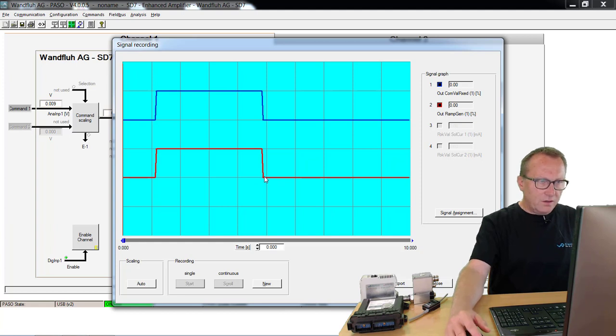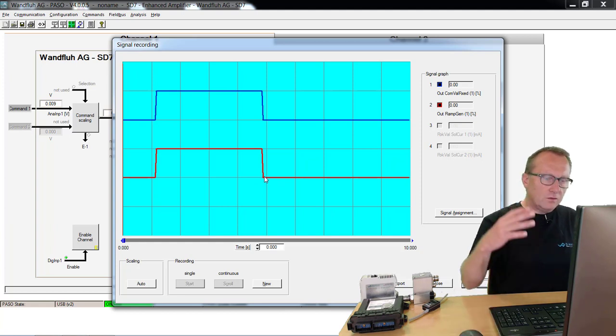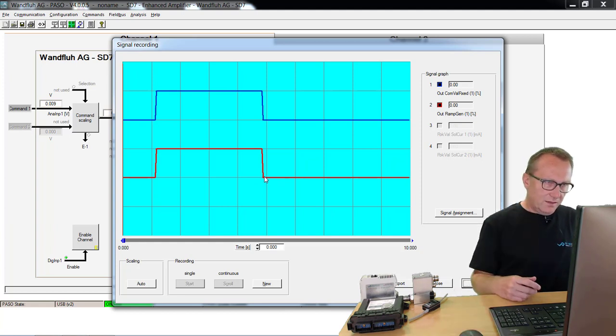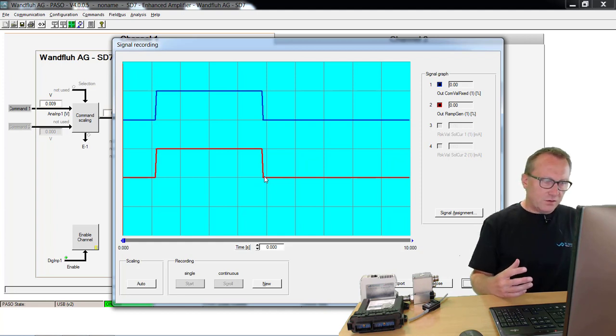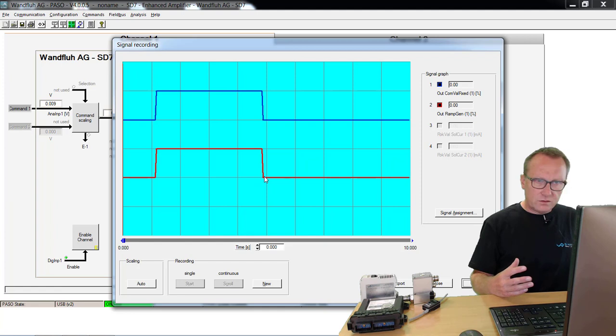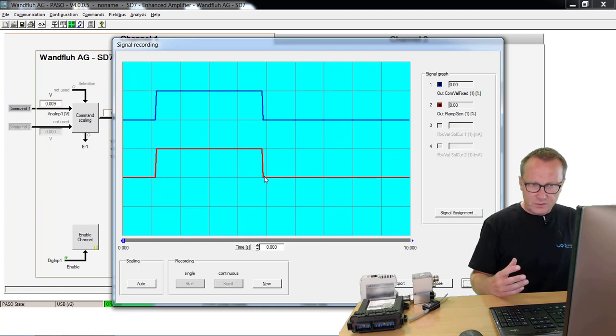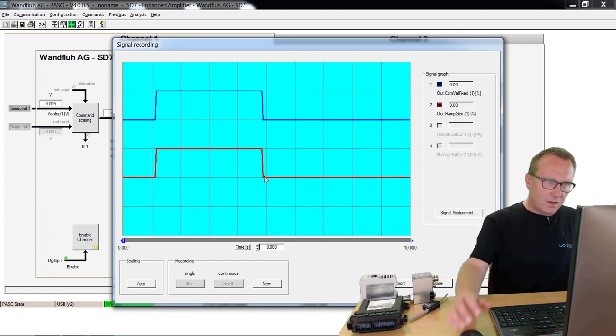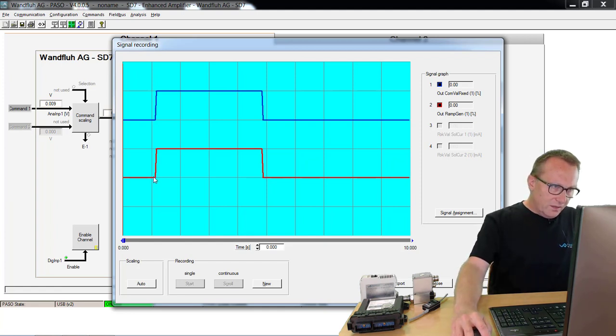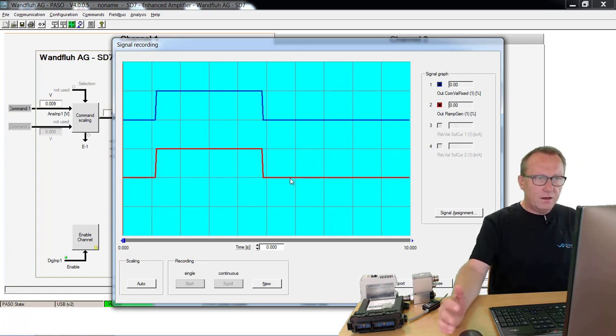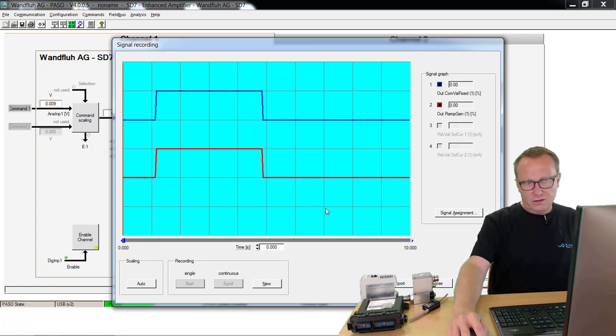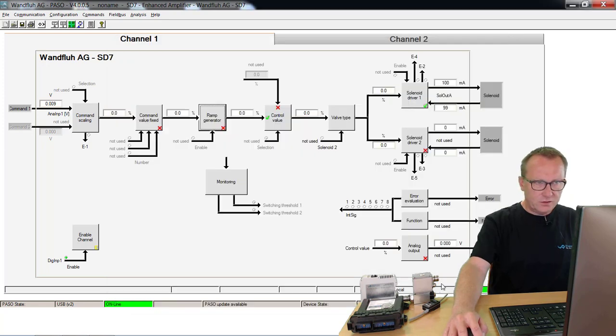This can be dangerous. If I have a big load on my system, then this can create some pressure peaks on the system which are dangerous because some other components can be damaged with that. I should make this switch on or switch off smoother, and for that I can use the ramp function.